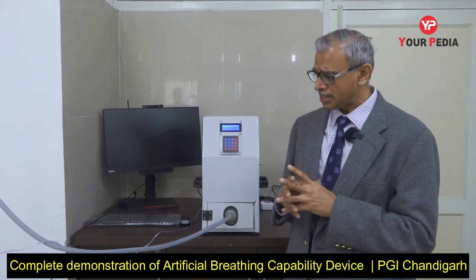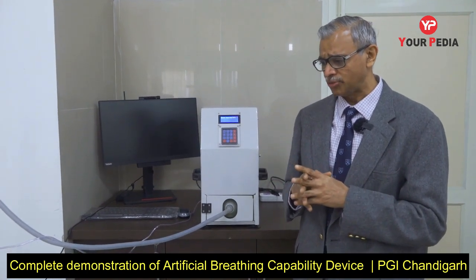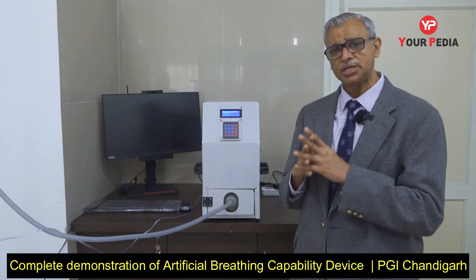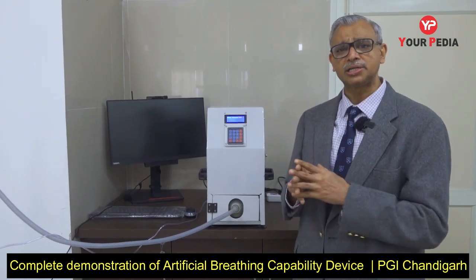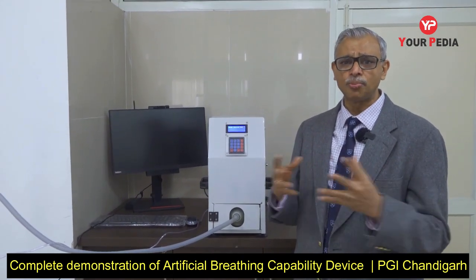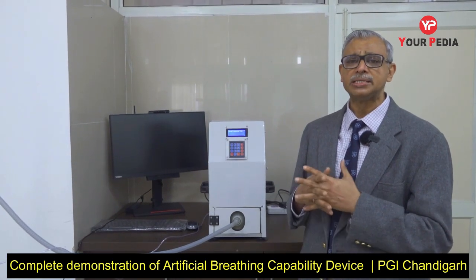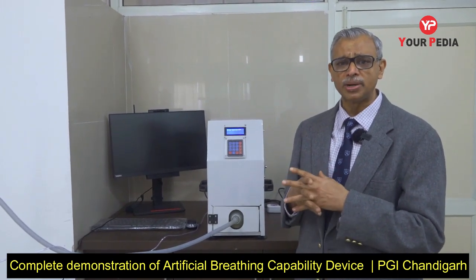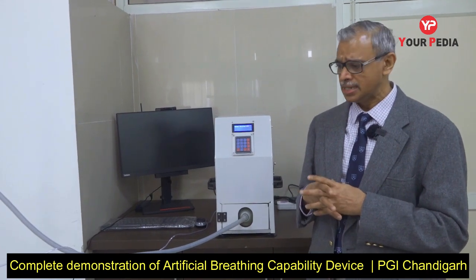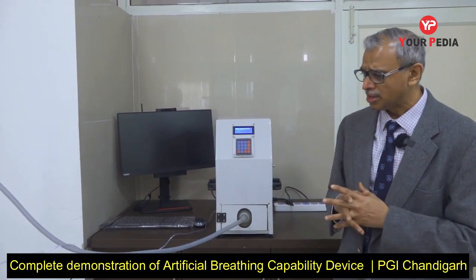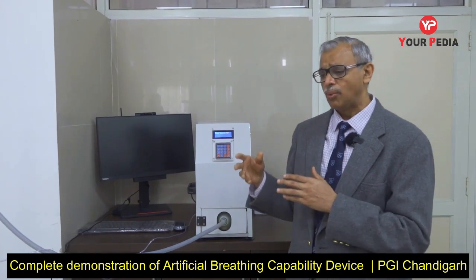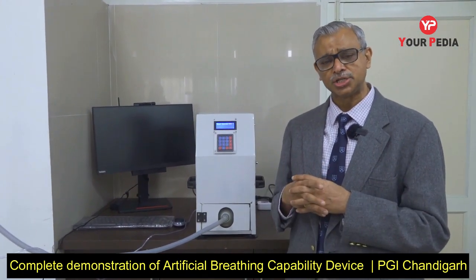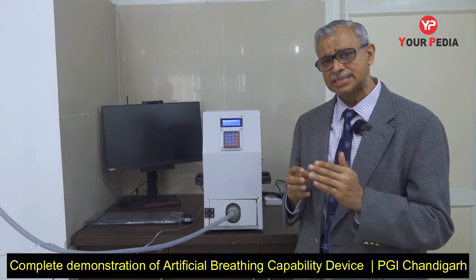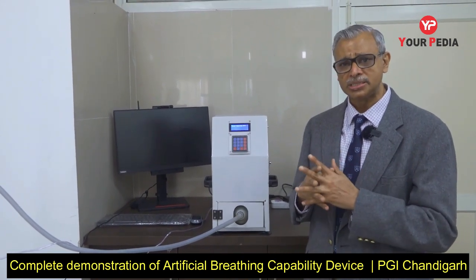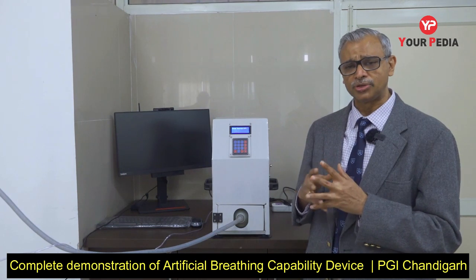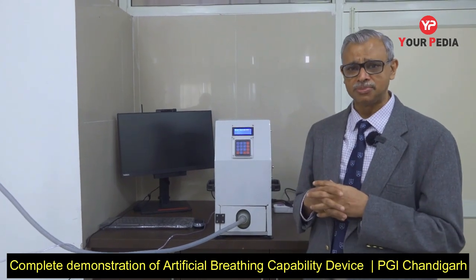The cough alert is a very important modification in this device. If a patient tends to cough while the ventilator is trying to deliver a breath, the two opposing pressures can cancel each other, and sometimes can even create volume and pressure effects on the lungs of a patient. So this device has a nice mechanism wherein if the patient tends to cough while the ventilator is trying to deliver ventilation, the device detects it, cuts off automatically for a preset duration of time, and then resumes with the same settings.